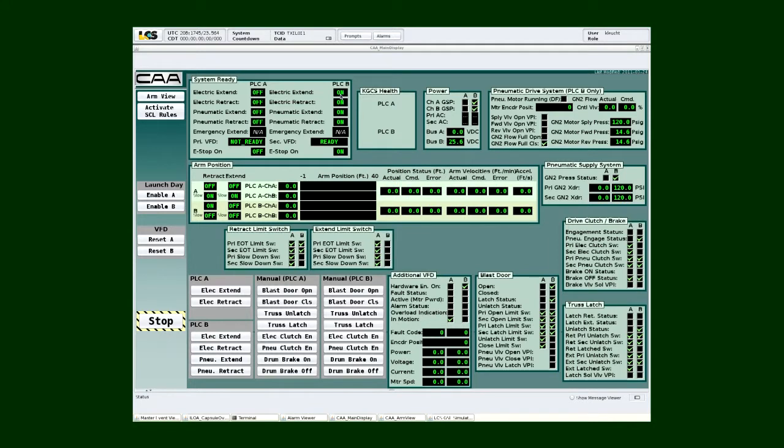The electric drive system consists of a single electric motor and two different variable frequency drives, which we call VFDs, which provide the speed control for normal operations and high speed motion for emergency operations. System A only controls the electric drive portion. System B controls both the electric drive system and the pneumatic drive system. And for that reason, PLC B is going to be the simulated subsystem that we're going to be monitoring today. So as I operate the system, please be aware that you will notice that PLC A information on the screen remains static and only PLC B items change, because our simulation is only enabled on PLC B.